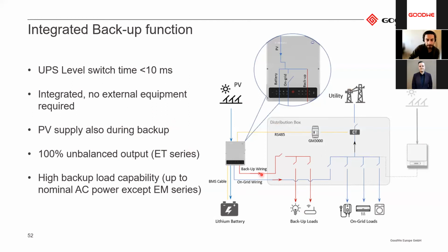It's also important to mention that the load you can install on the backup output is usually limited to the inverter capacity, and not more. For the 3-phase inverter, it's 1/3 per phase. So if you have a 10 kilowatt ET inverter and want to add some loads on the backup side to always be running, even if the grid is out, the maximum loads you can add is 3.3 kilowatt per phase. If you exceed this amount, then the inverter will try to power the loads but fail, and then will pause its operation for a certain amount of time and then try again. After it has tried a couple of times, it will stop trying and you need to reset the inverter. So this means that the inverter is not an off-grid inverter in any way. It's an on-grid inverter, but it supports backup.